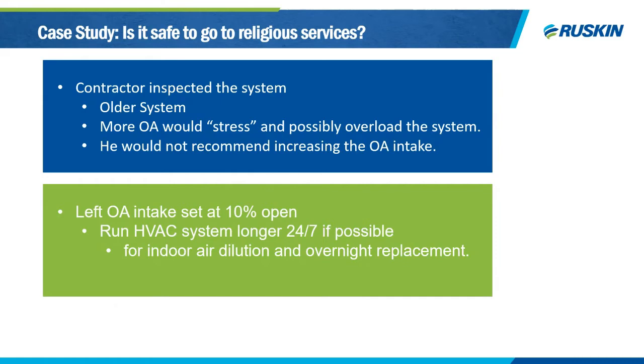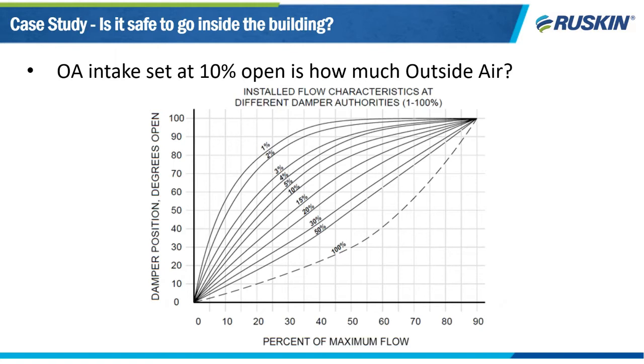Next slide, please. A fixed outside air damper is the most expensive way to control the air intake, especially in a building like a synagogue or a church, where the space is often unoccupied for 6 days a week. When the building is closed and no one's inside, there's no outside air required for that space. Having a fixed outside air damper is like going on vacation for the week, leaving your home air conditioner system running and with the bedroom window open. Unfortunately, you're not there to enjoy the AC or breathe the fresh air. And as you can imagine, this is very expensive.